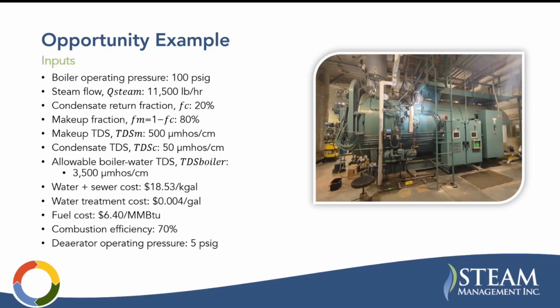So water treatment systems can be expensive. I would say they're probably going to be more expensive to implement than this. And then you're still going to have some blowdown. So this is going to capture a lot of the energy in the blowdown, whereas with improved water treatment, you might drop your blowdown from 4% to 2% or something. Whereas here, maybe you're capturing 80 to 90% of the energy, right? And also eliminating the tempering water. So I don't know, that's something to evaluate for sure.